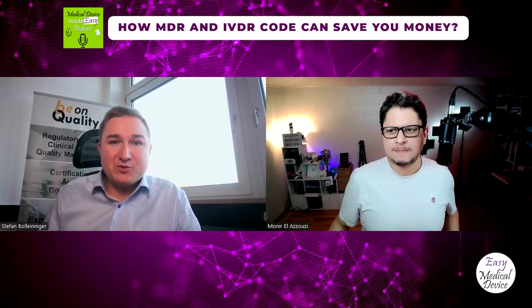Exactly. And now we come to the point where the codes are good and bad for your business. That code resembles the qualification of your certificate, what your certificate can achieve. So those codes are your foundation. They're not on the certificate, or only partly, but they reflect your indication-based EMDN codes. And based on those EMDN codes and the overall codes, it goes about what will be needed in a sampling or in an update of the certificate.